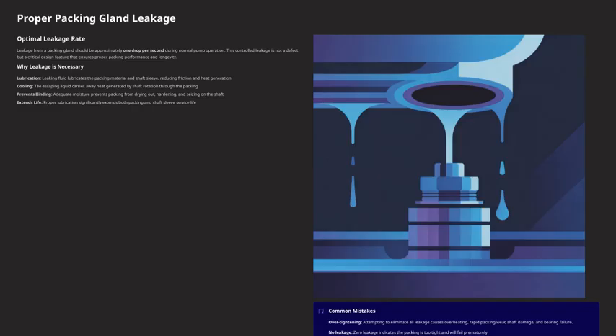Now, let's address common mistakes. Over-tightening the gland to eliminate all leakage might seem like a good idea, but it actually causes problems: overheating, rapid wear, shaft damage, and even bearing failure. On the other hand, zero leakage suggests the packing is too tight and will likely fail early. Conversely, too much leakage, more than 1 drop per second, wastes water and could mean the packing is worn out and needs replacing.